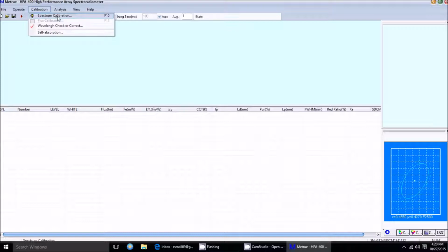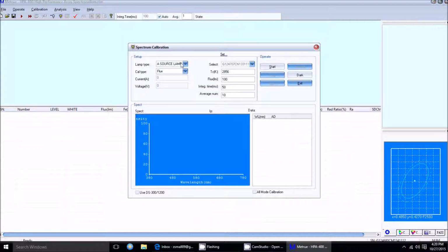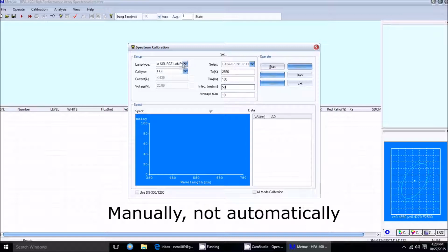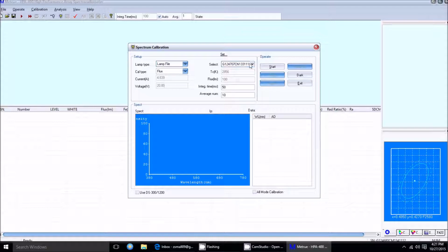Okay, so I can now hit spectrum calibration. You'll see here that I can input the data for my lamp, or I can choose a lamp file. So here you just have to hit whatever calibration type it is, which for us is flux, and then you can put in the information manually, or as I showed you earlier during the software installation and setup, you can hit lamp file, and I can choose the one here. So I only have one lamp file. This is the same serial number as my calibration lamp. So I can select that one, and that's it. You can hit start.